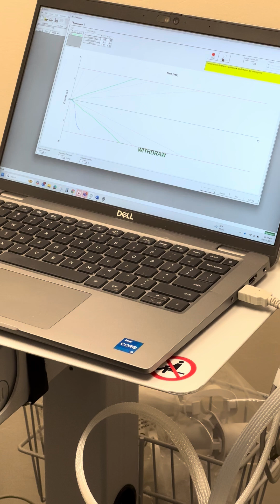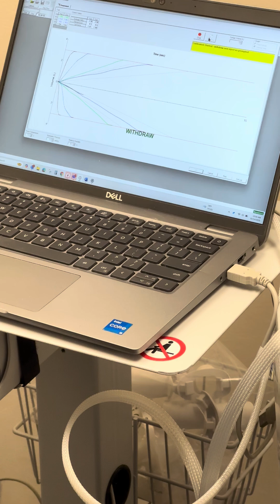Again, it doesn't matter the order that you do these in. And even though there are only 4 red dotted lines, you're actually going to do 5 withdrawals and 5 injects. So you just keep going basically until you don't have prompts, until you've satisfied all the withdrawal and inject prompts. So the slower I move it, the more to the right my flow line will go. The faster I move the plunger, the more to the left my flow line will be.